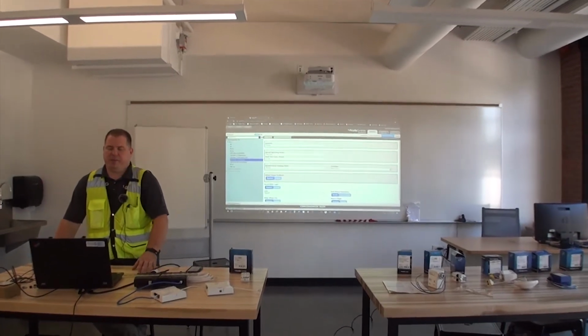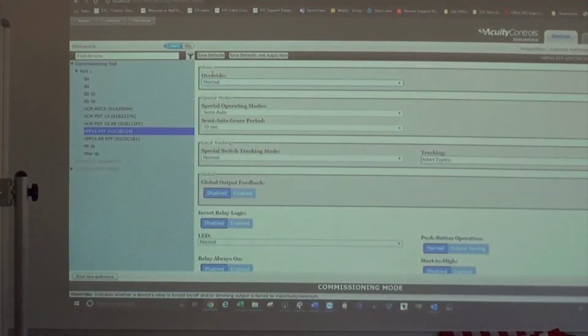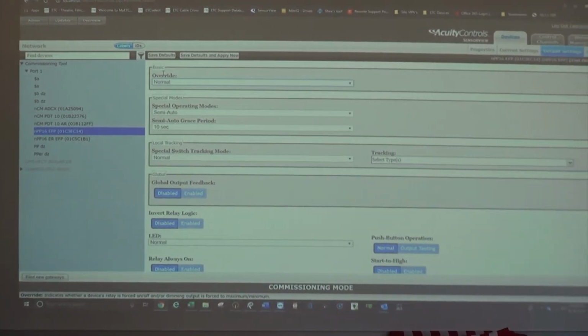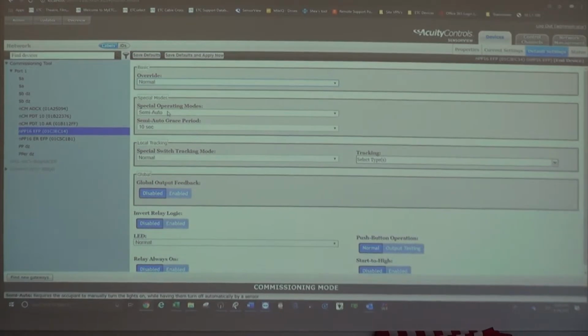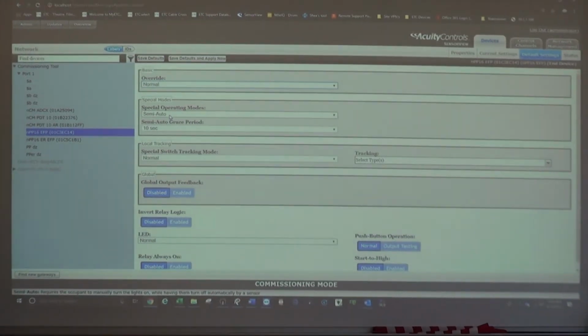So, special operating mode is where we determine whether things are vacancy or occupancy. And if you notice, that setting is actually in the power pack, not the occupancy sensor, because you're telling the power pack how to behave in response to an occupancy state. So you can have one power pack set to manual on and another power pack in the same space set to auto on, because that setting lives in the power pack. 90% of all your settings are in power packs. So if you have two different functions in one room, it's going to have separate power packs for that.